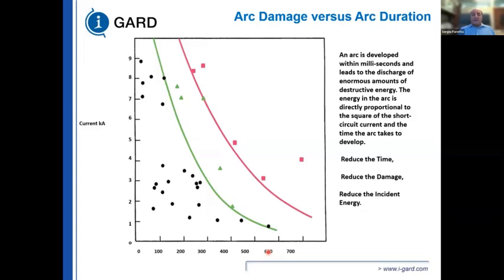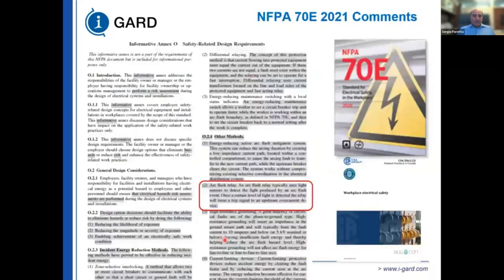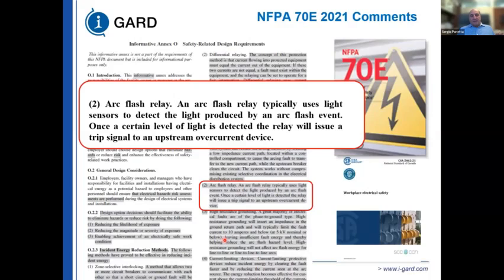So when you're at 40,000 amps, it takes 83 milliseconds to clear the fault, open the breaker, but you have to detect the fault. If it goes undetected, you're going to have a lot of damage at the point of fault. So to minimize the damage to equipment, and more importantly, to minimize the incident energy that your personnel is exposed to, we have arc flash relays. Arc flash relays don't rely on standard overcurrent devices to operate your breakers. They're fast detecting, light sensing equipment to detect the presence of an arcing fault and to clear the system of that fault right away.